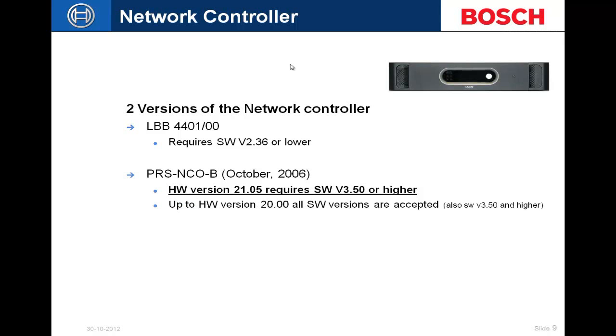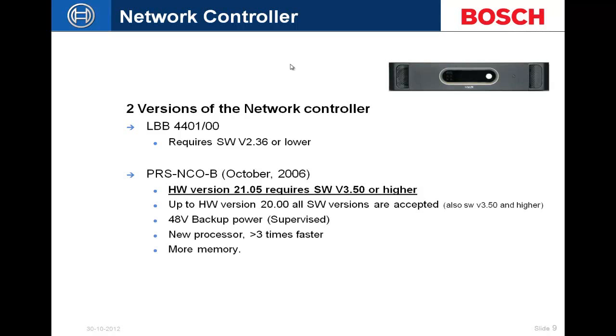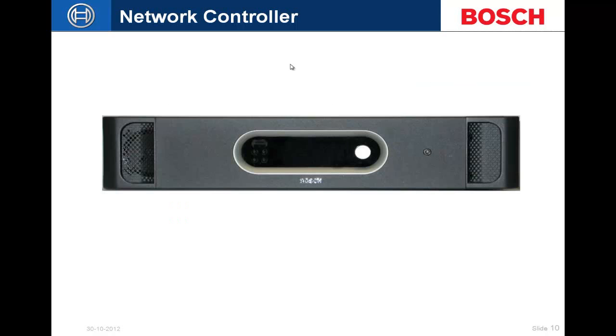If you're going out on a retrofit and putting in a new network controller, and the existing gear has version 3.4 firmware, upgrade the old gear to match the 3.5 firmware rather than downgrading the network controller back to 3.4 — just bring everything up to the newer version. It has a 48-volt DC battery backup input that is also a supervised power input, and it has a new, faster processor.